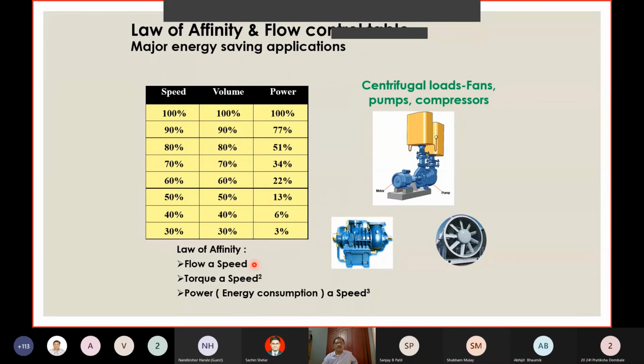As per the law of affinity, flow is directly proportional to the speed. Torque is proportional to the square of the speed, and power is proportional to the cube of the speed. So if you are able to reduce the speed by 50%, your power saving will be much higher. I don't know whether I made a mistake in using a slide here, but actually it will be much higher. That is what I am trying to show here.